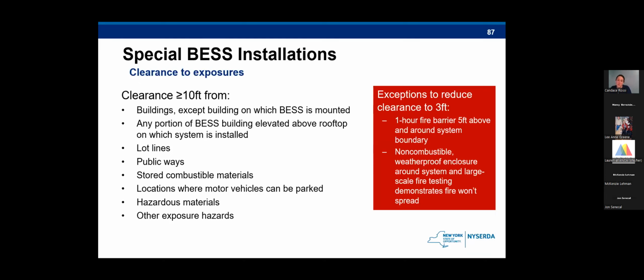So both of these special installations have to meet this requirement for clearance to exposures. So once again, they have to be 10 feet from everything that's listed on the slide. So buildings, lot lines, public ways. And then there are also exceptions that would allow the distance to be reduced to 3 feet if they meet those requirements. So if they have that 1 hour barrier 5 feet above and around the system boundary, or if they have a non-combustible weatherproof enclosure around the system, and large scale fire testing demonstrates that if there is a fire, it would not spread, they could have a reduced distance.